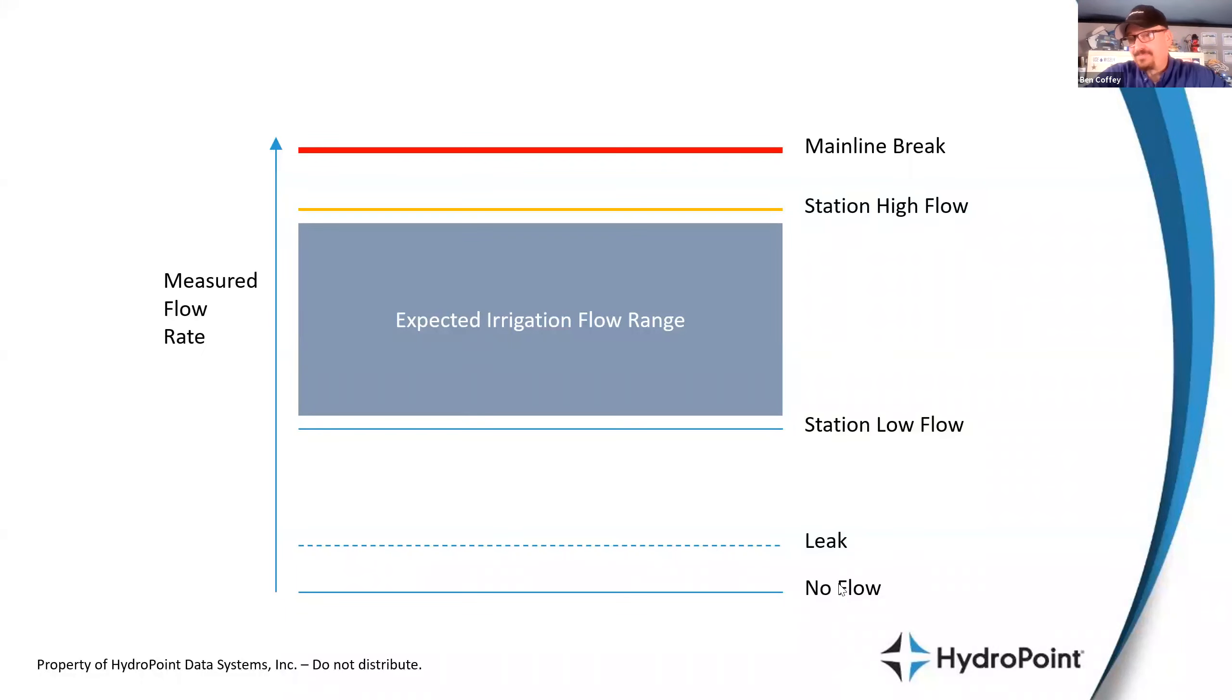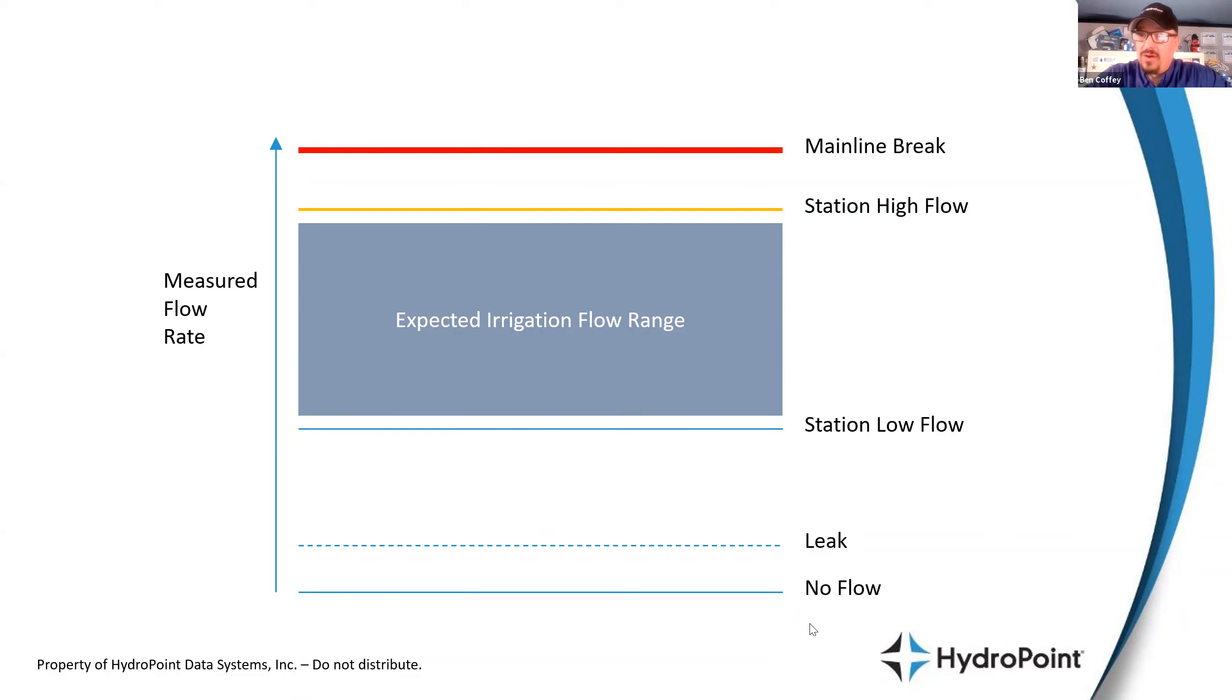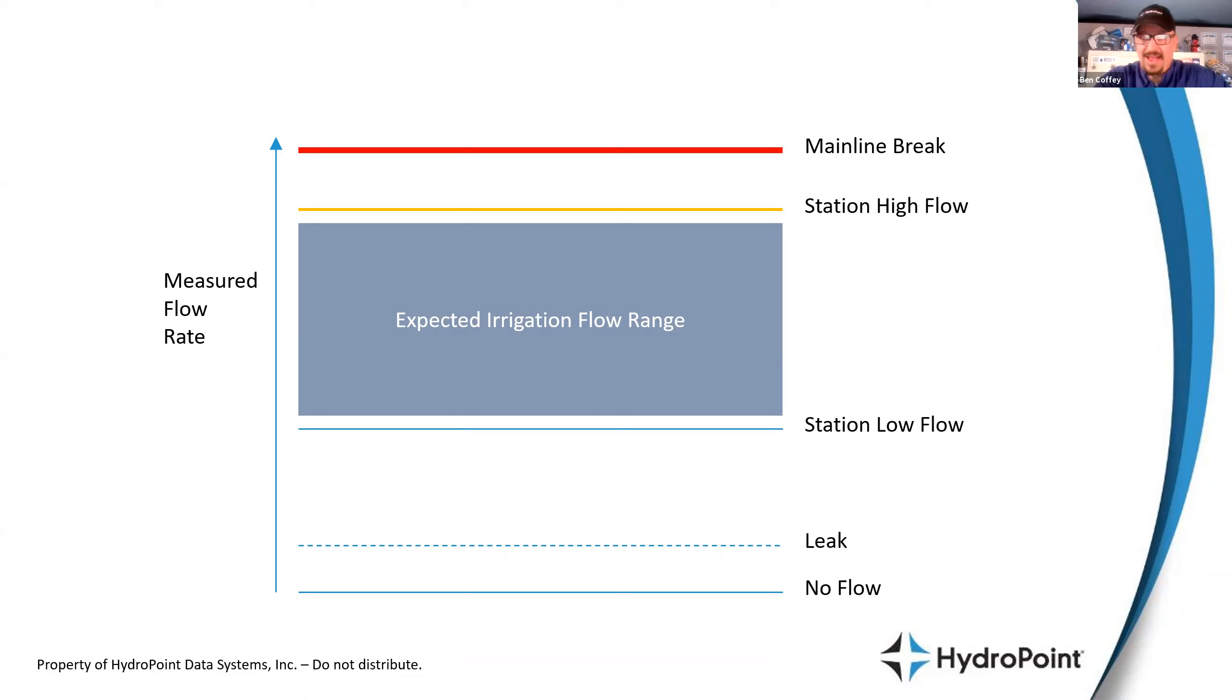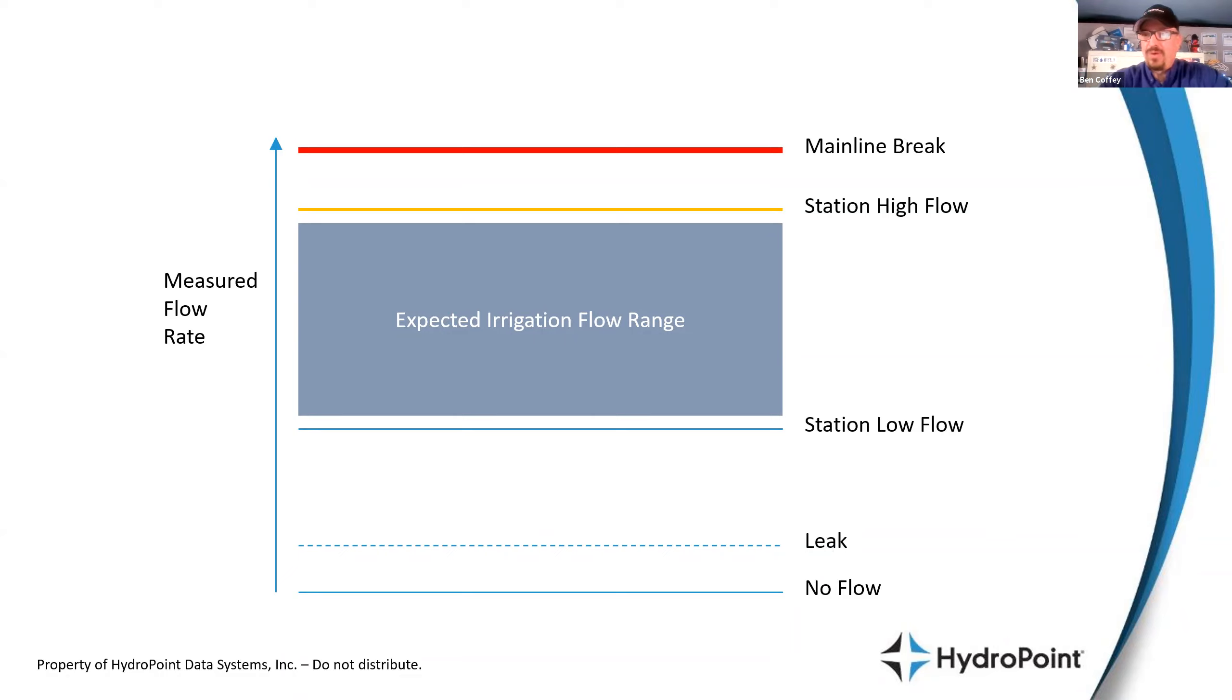The mainline break threshold is a system-wide do not pass kind of level. But then for every station, we'll have a station high flow and a low flow. If it wavers too far away from the expected range, we'll be able to manage that. As well as leak is universal, that means that water's running during non-irrigation hours, but no flow is specific for station. We tried to prompt irrigation, we got nothing out. All these can lead to guys like Scott out in the field chasing down issues.